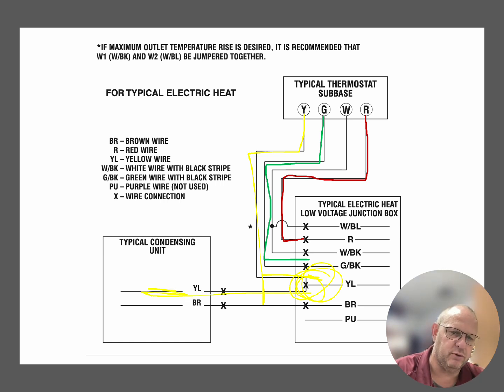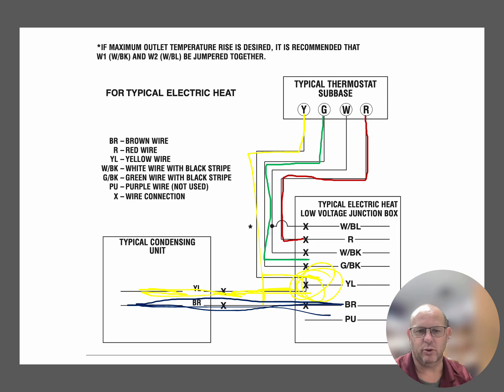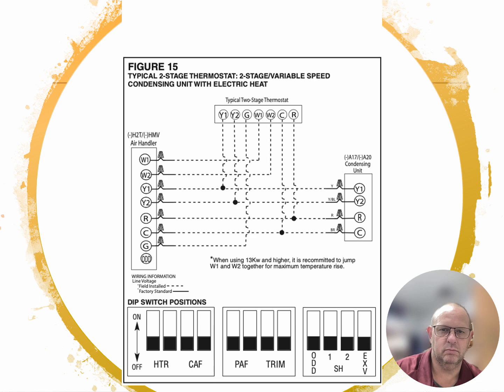After that, you're going to have a brown wire that's going to come back, or a blue wire that's going to come back as you're completing the circuit for the outdoor unit. And that's typically how your low voltage will be hooked up. So what we have here is a 2-stage unit, a 2-stage air conditioning unit. Notice that we have an indoor unit, an air handler, a 2-stage thermostat, and then a 2-stage outdoor unit.